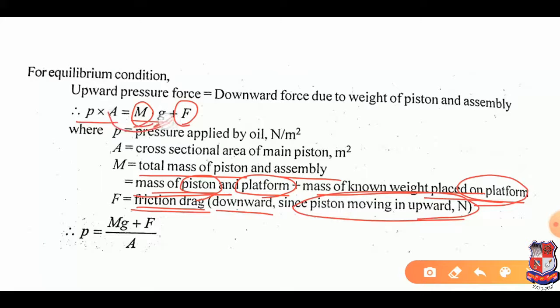So we divide by this A, we will get pressure applied by oil by this equation. So pressure calculated by above equation is actual pressure applied to gauge under calibration. The comparison is carried out between pressure calculated from above equation and pressure indicated on the dial gauge at different pressure. By changing amount of weight on the platform, we can calibrate the Bourdon tube, or we can identify the accuracy. Now there are some factors by which the accuracy of dead weight tester is affected.